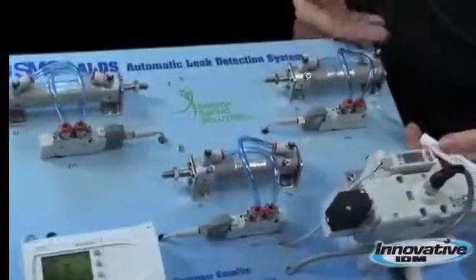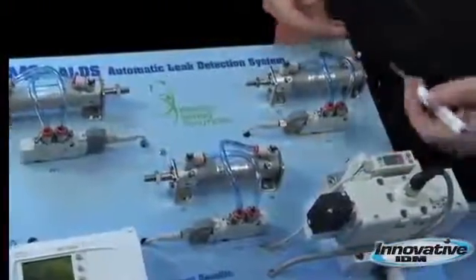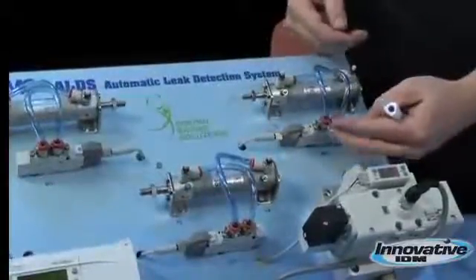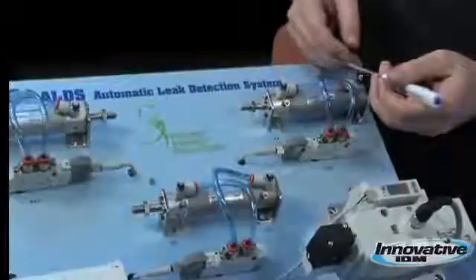On this panel here, we can locate T4 and now we know that the leak is located within this section of the piece of equipment only. We can eliminate the leak from the other part because we only have to look here.